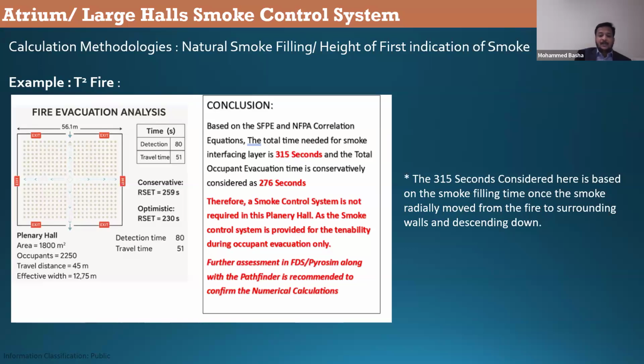So the total occupant evacuation time is conservatively considered as 276 seconds. Of course, we have software to do this. I will show you if we have time at the end of this session. Therefore, a smoke control system is not required in the plenary hall, as the smoke control system is provided for tenability during occupant evacuation only.